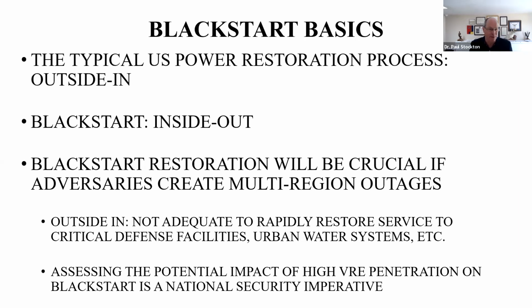Black Start is the opposite. Instead of importing power from the periphery of the outage area, you do it from inside the blacked out region. That's the huge advantage of Black Start in a wide area power outage, because if you can restart from the center, potentially of an entire interconnection, you can get grid-provided power back to critical loads much more quickly than with traditional outside-in restoration.